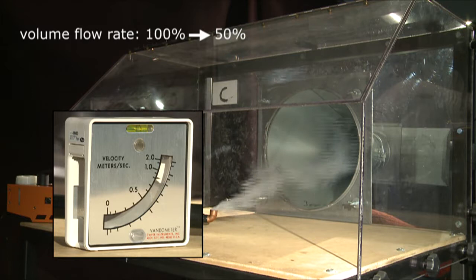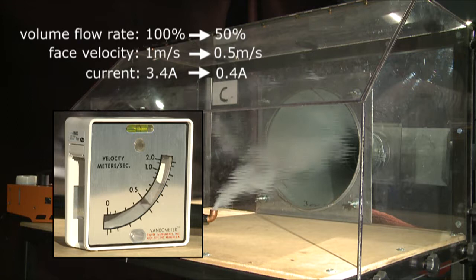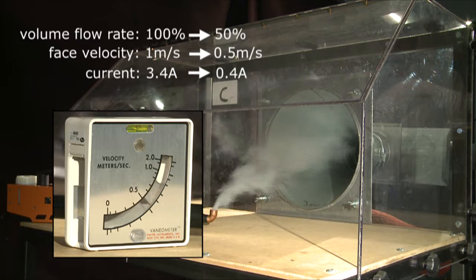The volume flow rate has been halved. This reduces face velocity from 1 meter per second to 0.5 meters per second. The current has been reduced from 3.4 amps to 0.4 amps, a power saving of 88%, which lowers the running cost of the LEV system and reduces its carbon footprint.